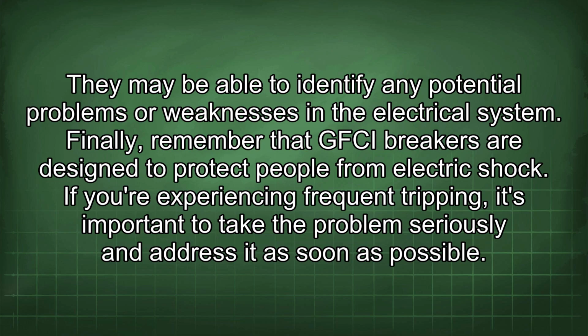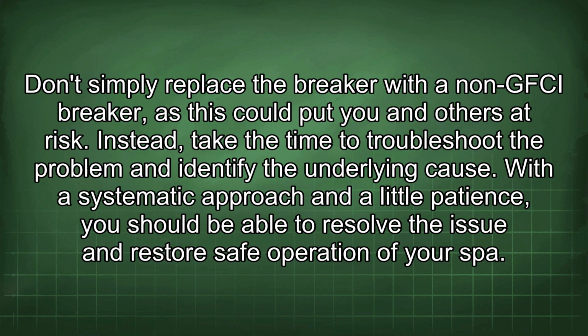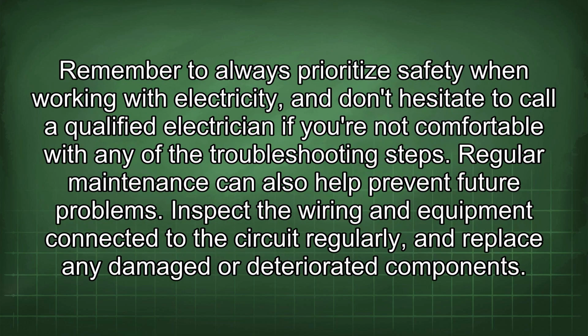Finally, remember that GFCI breakers are designed to protect people from electric shock. If you're experiencing frequent tripping, it's important to take the problem seriously and address it as soon as possible. Don't simply replace the breaker with a non-GFCI breaker, as this could put you and others at risk. Instead, take the time to troubleshoot the problem and identify the underlying cause. With a systematic approach and a little patience, you should be able to resolve the issue and restore safe operation of your spa. Remember to always prioritize safety when working with electricity, and don't hesitate to call a qualified electrician if you're not comfortable with any of the troubleshooting steps.